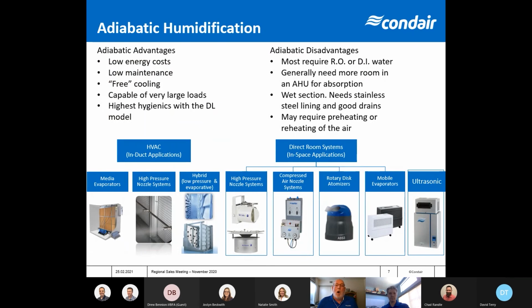Next page here, we'll talk about our adiabatic systems. So as I mentioned at the start, every single one of these humidifiers here, because we're not boiling water, we're just applying water directly to the air, just evaporating it using the heat energy in the air. So these are going to cool the air as well as humidify. So we're going to generate 1,000 BTUs of cooling for every pound per hour of humidification that we generate. That might be a good thing, might be not so good, depending on what our application is. We might have to do some preheating or reheating of the air if we have really big loads, because we're going to make a lot of cooling.